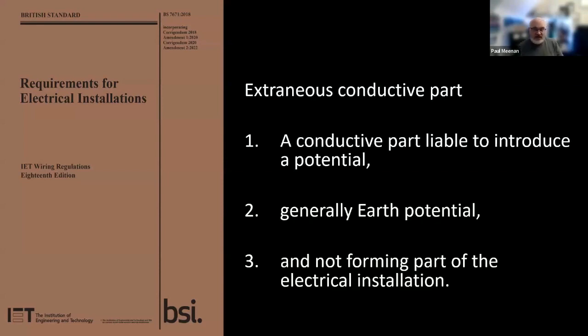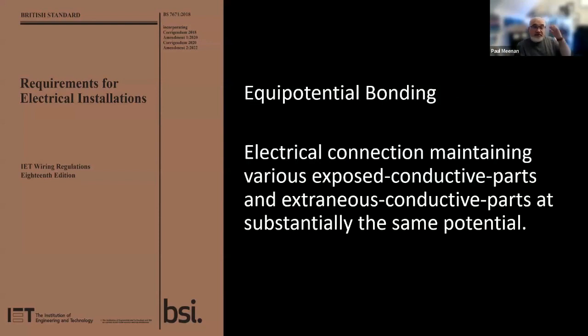But then if we look at extraneous conductive parts, when I was younger I spent a lot of time trying to work out what the difference between the two is. Again, use the rule of 3, break it up, highlight it. An extraneous conductive part is a conductive part liable to introduce a potential, a voltage. It's generally at earth potential, so in theory a pipe that comes out of the ground should be at 0 volts, and not forming part of the electrical installation. So if you have an oil pipe, a gas pipe, or a water pipe that comes in from the ground, we assume that it is at 0 volts, so it's extraneous. But what do we do then to ensure safety, so that it doesn't become part of a path? So what we do is equipotential bonding.